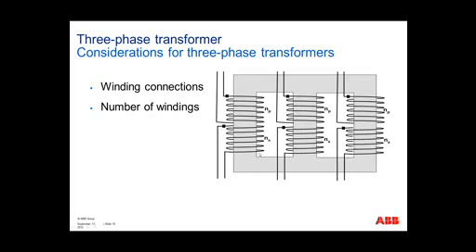If you had a tertiary winding, the windings would be connected underneath the low side winding, associated to its individual phases. Also, you need to identify what type of connections your transformer is. Whether it's a Wye-Wye, Wye-Delta, or Delta-Wye is an important consideration, and we're going to see that in the next couple of slides.